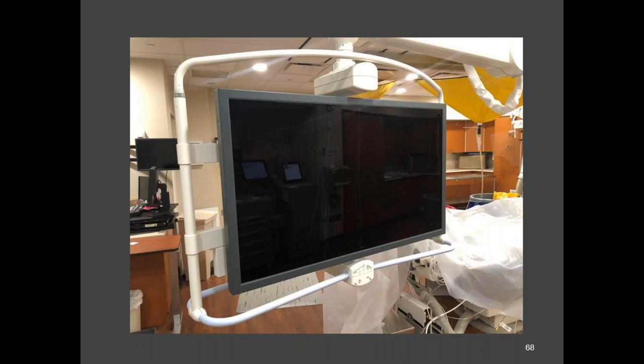So I go over to the back and flick the power off and on. And yeah, that's what I got. I ran my hand down under the base of it where the vents are to cool it, and my hand had this kind of gooey, wet stuff coming off of it. I was going like, yeah, this thing's gone. The IR manager finally showed up, and he laughed. He said, yeah, they said it hung on there for a while. It was on and had numbers on it, and then they came back later, and it was like this. So that's about a $90,000 to $100,000 item right there.